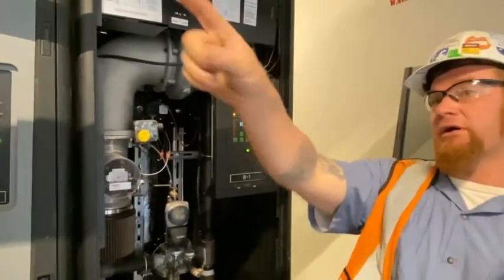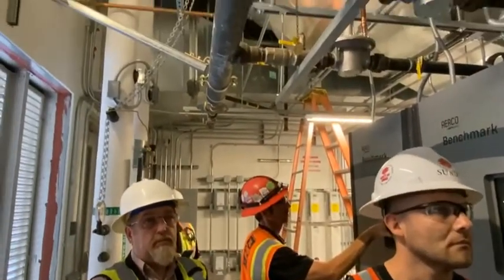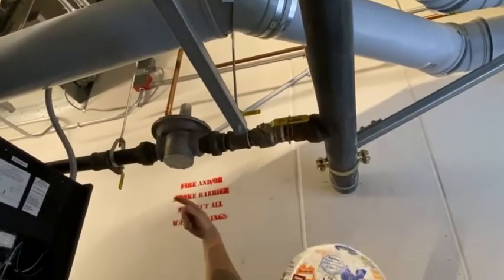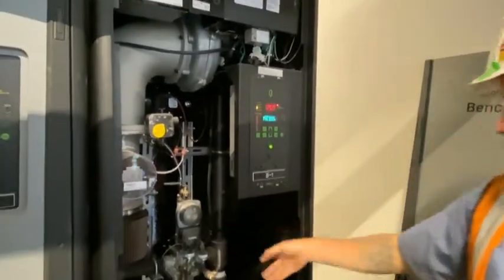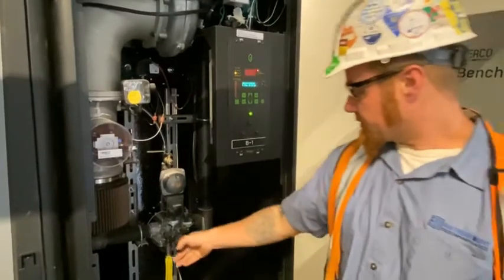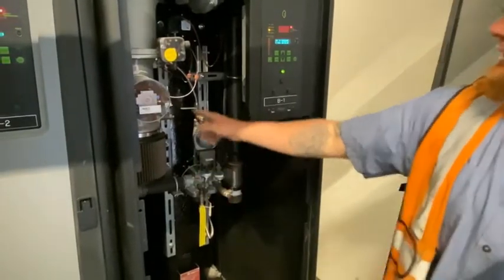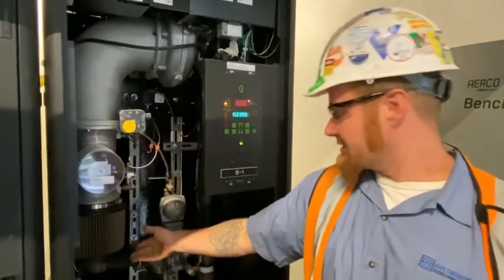Gas is coming in — we have our main regulator, and then we have step-down regulators, which are flow-through regulators provided by AERCO. These need to be set while we're actually getting gas through them. We have gas coming in at about seven and a half to eight pounds pressure. There's a safety shut-off — for any power loss or fault, that plunger drops down and shuts off the gas to the system. We're stepping down to about three and a half pounds manifold pressure, and then we have our air-fuel mixing valve.